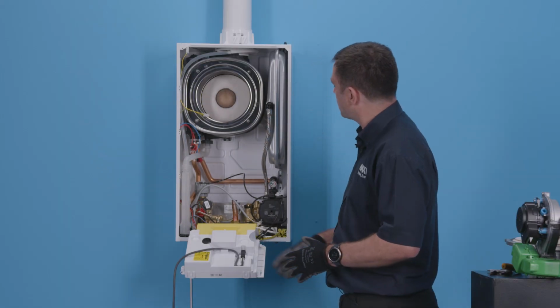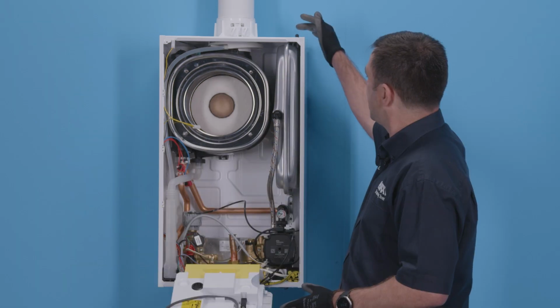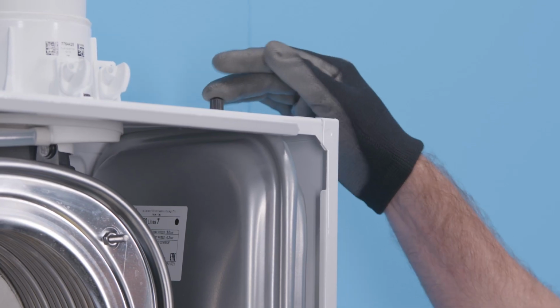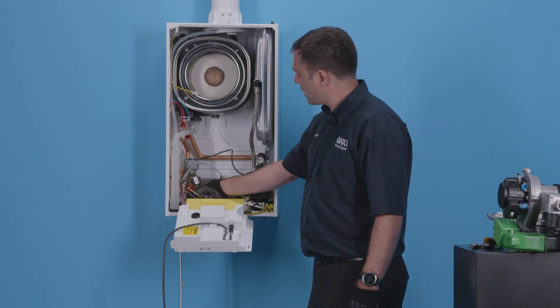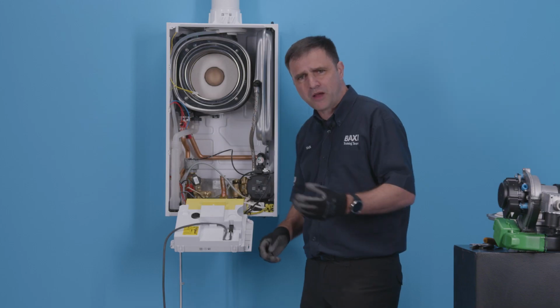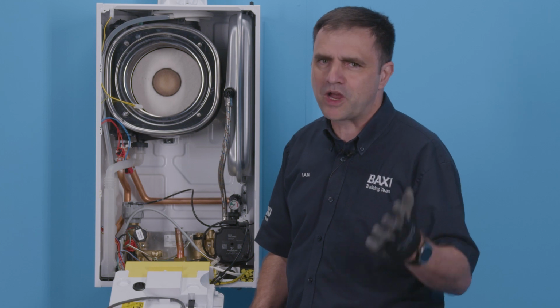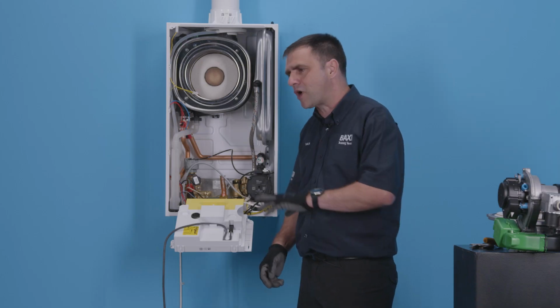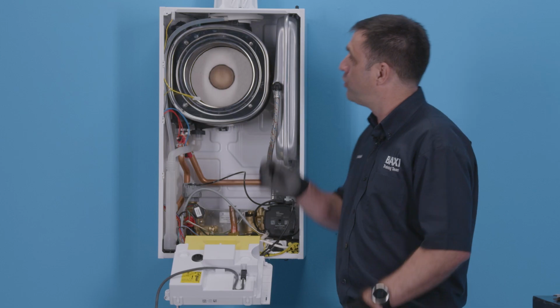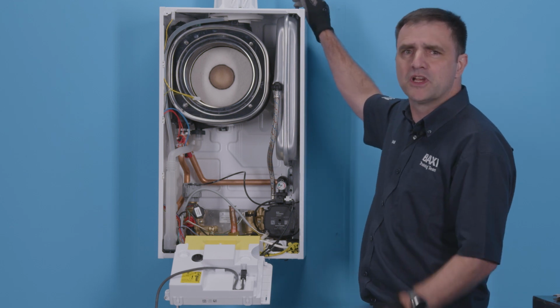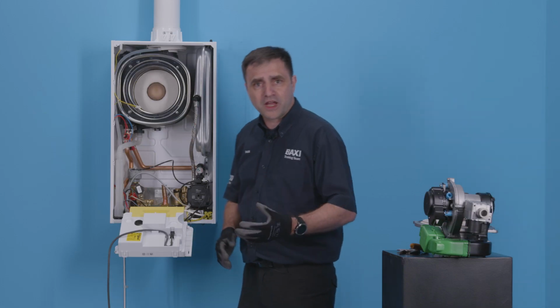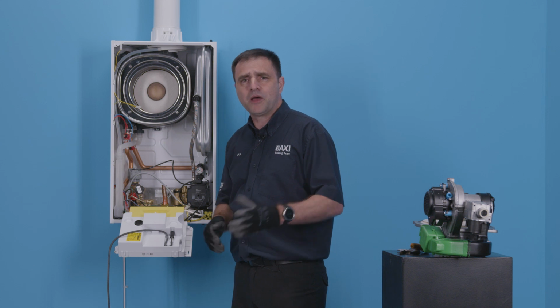On the service, it's always good practice to check my expansion vessel as well. Test point on the outside of the case, making it very easy to charge. Drain the water out through the drain point here, charge it up to 0.7 to 1 bar. Fundamentally, we only need 0.7. If you go to 1 bar, don't worry about the hiss as you release a Schrader valve. Put some leak detector fluid on top of the Schrader valve just to make sure it's not leaking. Once I've done that, reassemble in reverse order and move on to your standard checks.